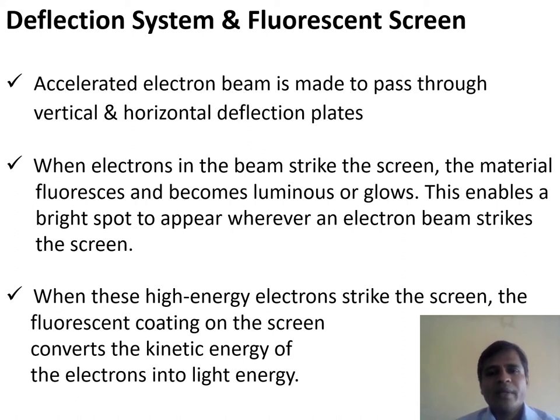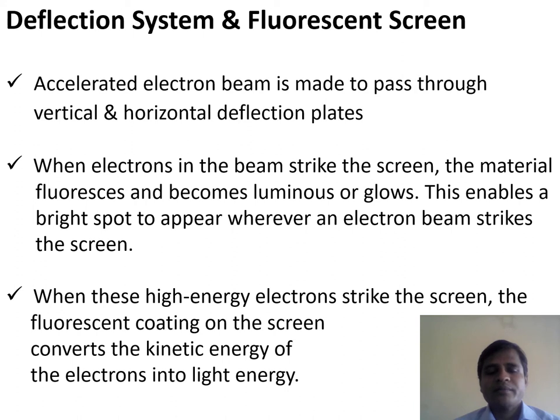The inner part of the fluorescent screen is coated with phosphor or zinc sulphide. When the electron beam strikes the screen, the material fluoresces and becomes luminous or glows, enabling a bright spot to appear wherever the electron beam strikes. The accelerated electrons carry kinetic energy due to their mass and velocity, and when these high-energy electrons strike the screen, the fluorescent coating converts their kinetic energy into light energy, producing a bright spot. This is how the CRO converts the electrical input signal into a visual signal.